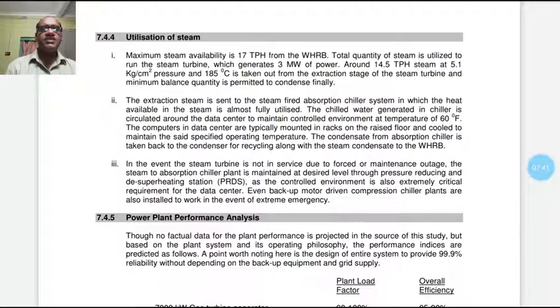The extraction steam is sent to the steam fired absorption chiller system, in which the heat available in the steam is almost fully utilized. The chilled water generated in the chiller is circulated around the data center to maintain a controlled environment at a temperature of 60 degrees Fahrenheit. The computers in data centers are typically mounted in racks on the raised floor and cooled to maintain the specified operating temperature. The condensate from the absorption chiller is taken back to the condenser for recycling along with steam condensate to the waste heat recovery boiler.